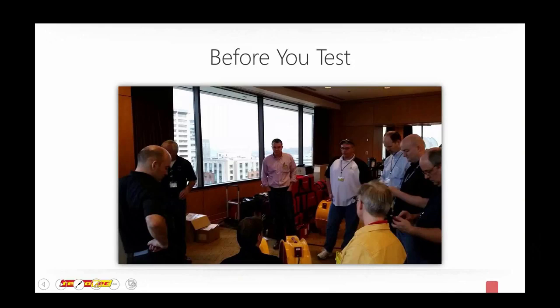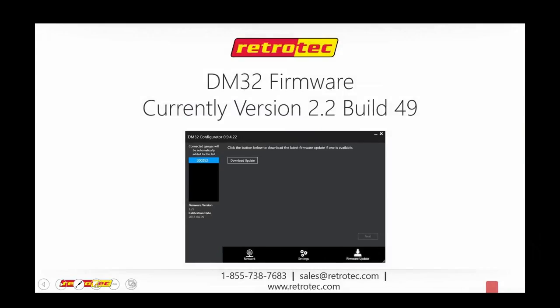Okay, well, let's go with a basic chronological approach to testing. Let's talk about some of the things you can do to problem solve or troubleshoot before the trouble even starts. As many of you know, the DM32, which is our newest gauge, only needs to be calibrated about every 5 years, because it can update firmware right online. Right now, the most current version is 2.2, build 49. If your DM32 is not the same build or version, just plug it into the gauge configurator, and it will check online to make sure it's up to date. That's the first thing you want to do: make sure you're using the most up-to-date software.